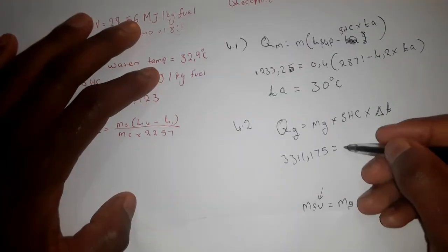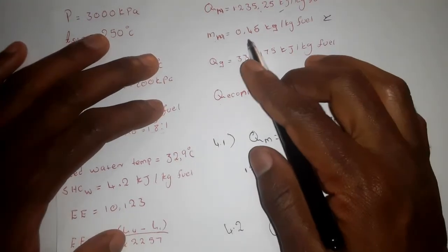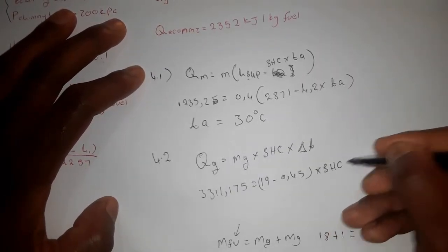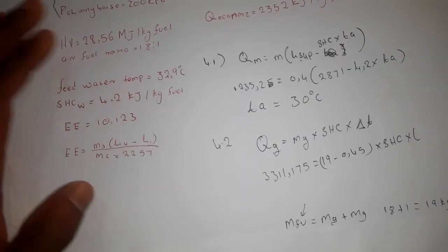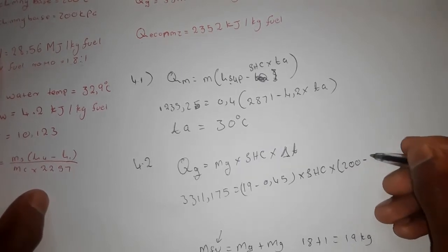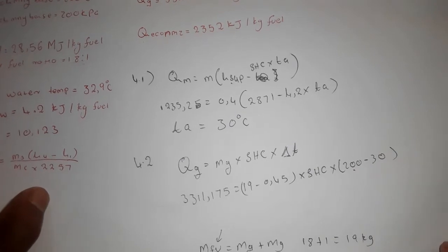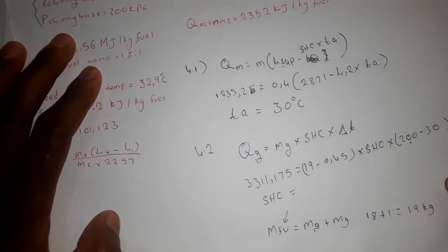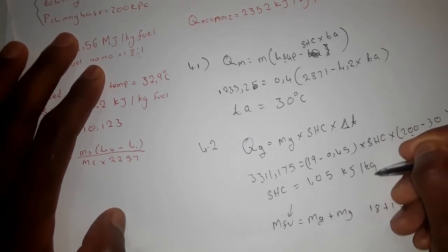The mass of dry gases is 19 minus the mass of moisture (0.45), giving 18.55 kg. The specific heat capacity is what we're solving for. The change in temperature is the chimney base temperature (200) minus the atmospheric temperature (30), which equals 170. I got the specific heat capacity equals 1.05 kilojoules per kg Kelvin.